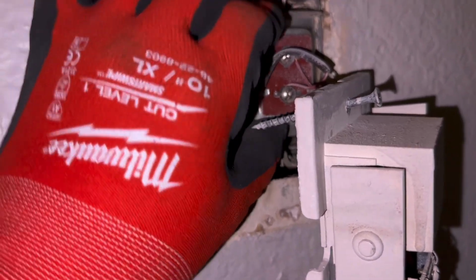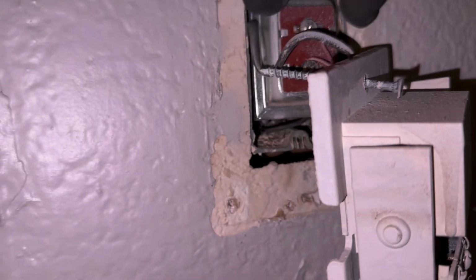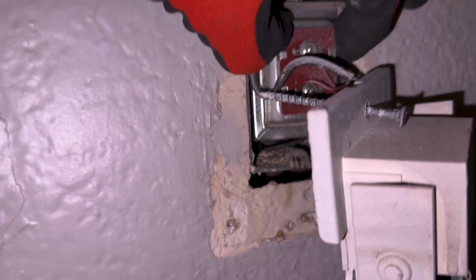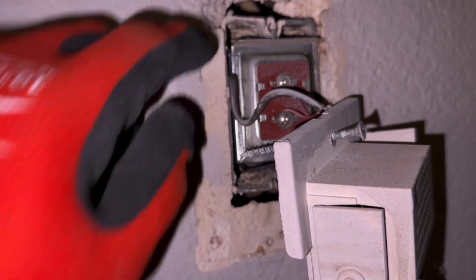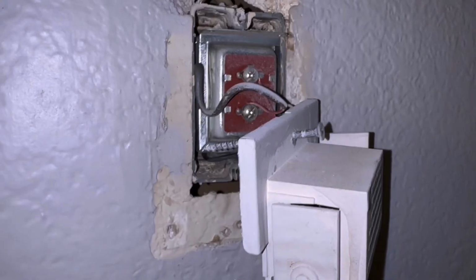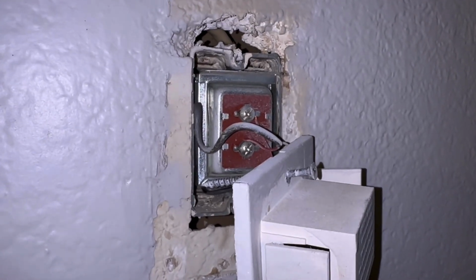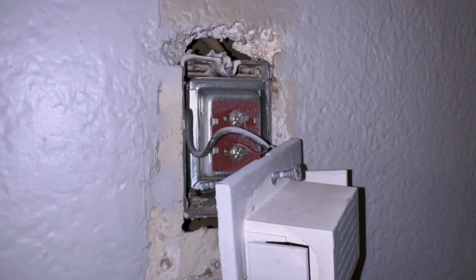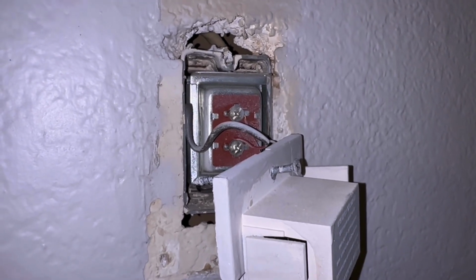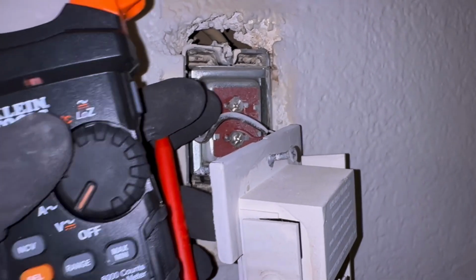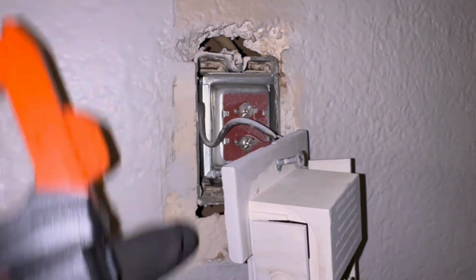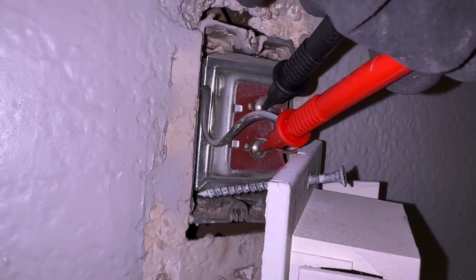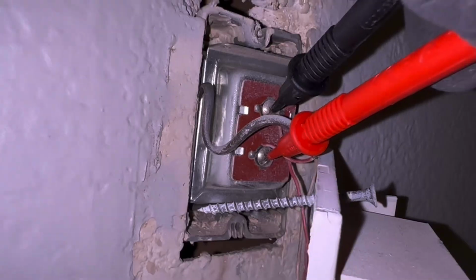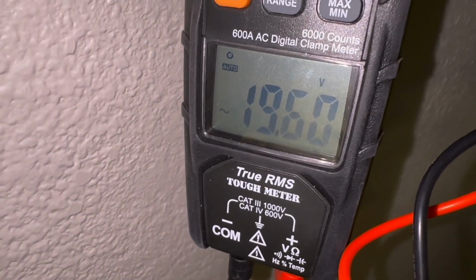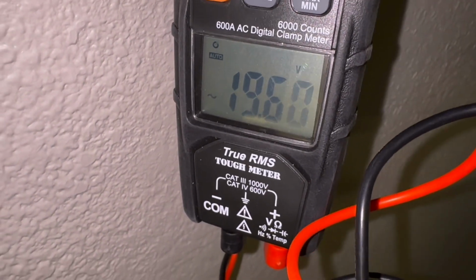What I'm going to do is I'm going to remove the transformer gently, and once I do that, that'll show me the 120 incoming volts. If you wanted to see if your transformer was working, what we would do at this point, specifically on the low voltage side, is we would use our multimeter and we would test these leads right here to see if we have low voltage. You can see here on the multimeter that we do have low voltage.